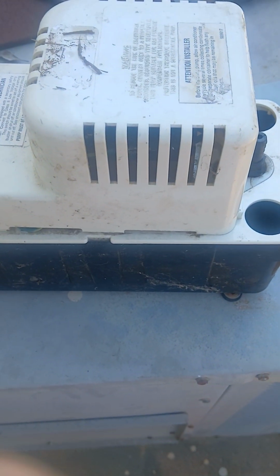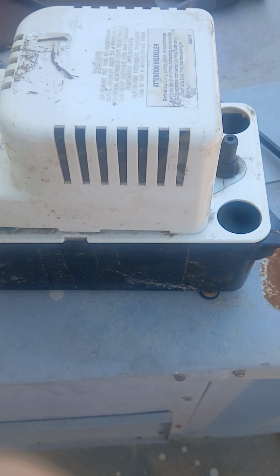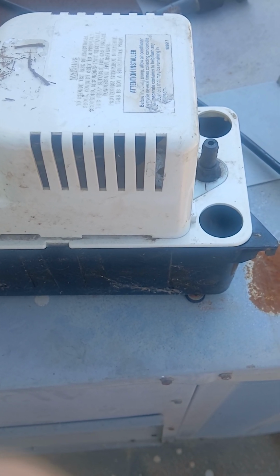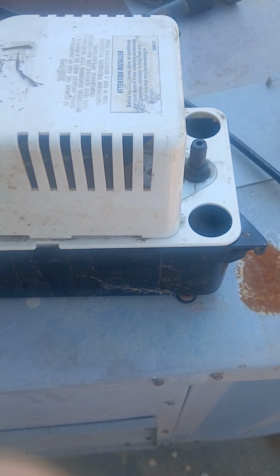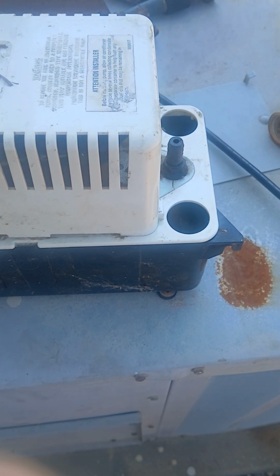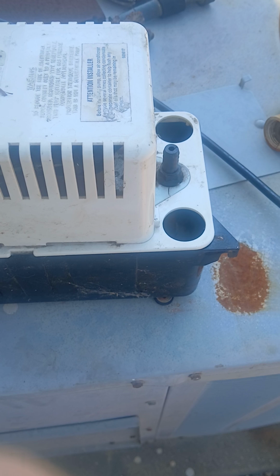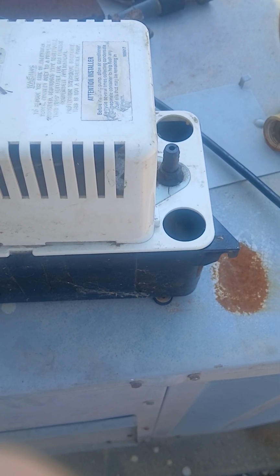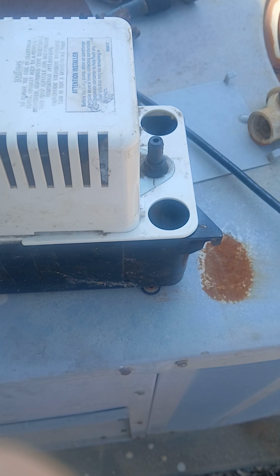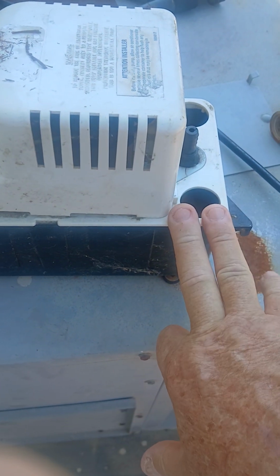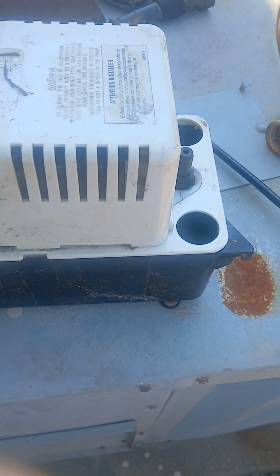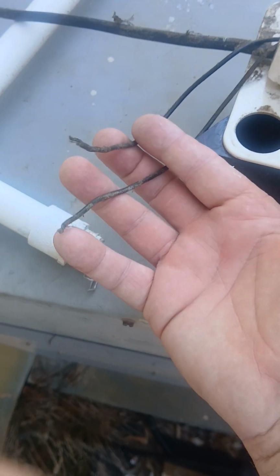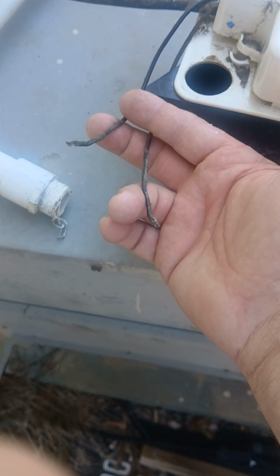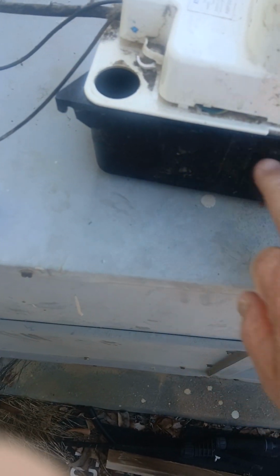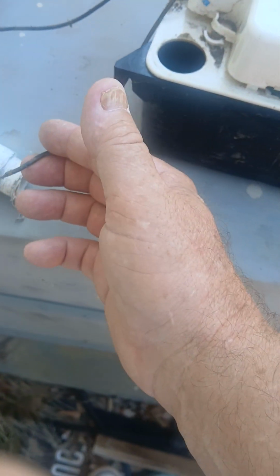So what happens after the entire HVAC system is shut down? Simply put, the unit stops running. So the A coil stops running, the refrigerant stops moving, the compressor stops moving. So hence, the HVAC system may not be able to extract the humidity out of the air. And if it's not running, it fills this out. So then you may need to call a technician to be able to diagnose it. So these two wires here, maybe you could split your reds, which would be your hot, on your low voltage side. If the water got here, it would turn it off, because voltage may not be able to go through.